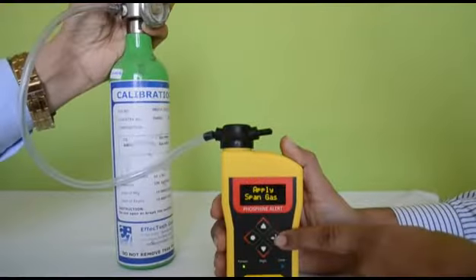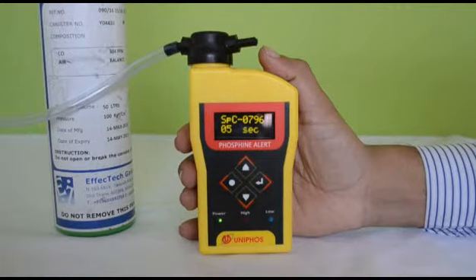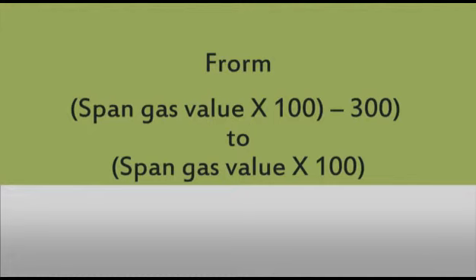and press enter key. Instrument will take samples of span gas for next 90 seconds and will show respective counts along with the timer. Span gas calibration will be successful only if the raised count at the end of 90 seconds falls in the acceptable range, else span calibration will fail and instrument will come back to measurement mode. The acceptable range of span count is from span gas value multiplied by 100 minus 300 to span gas value multiplied by 100.